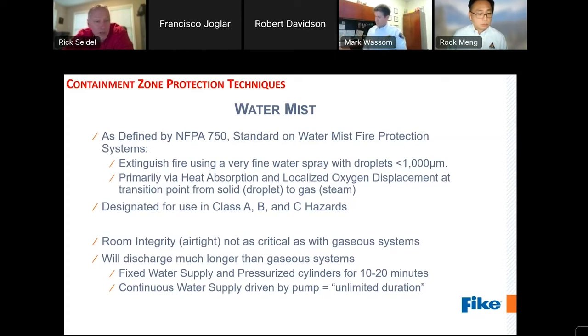We can use water mist. It's very effective in class A, B, and C hazards. The benefits of water mist is that room integrity, or the airtightness of the enclosure, is not as critical as it is with gaseous systems. And we can achieve a much longer duration of discharge with water mist than with gaseous systems.